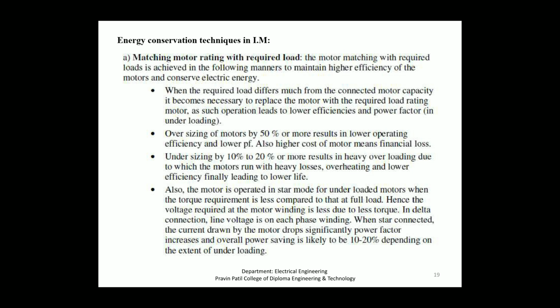Now we start the most important point in unit number 2, energy conservation techniques in induction motors. The first one: matching motor rating with required load. The motor is matched with the required load in the following manners to maintain higher efficiencies of the motor and conserve electric energy. When the required load differs much from the connected motor capacity, it becomes necessary to replace the motor with one of the required load rating.